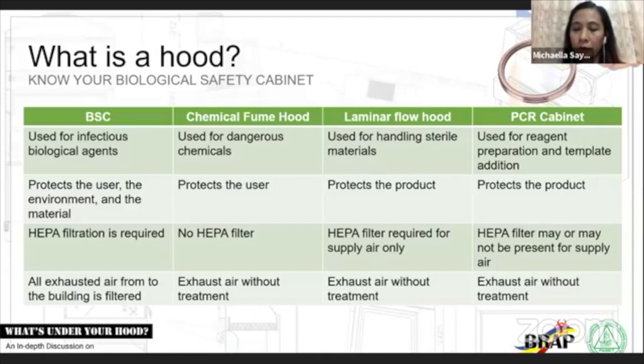PCR cabinets. Now, PCR cabinets, there are two types. One is the dead air chamber, and one is the filtered air. The filtered air works similarly to your laminar flow hood. And the dead air is simply a sterile cabinet with static air inside. So you just maintain the cleanliness of the internal chamber with your decontamination processes and your proper work procedures. And there is no need for filtration for this one.